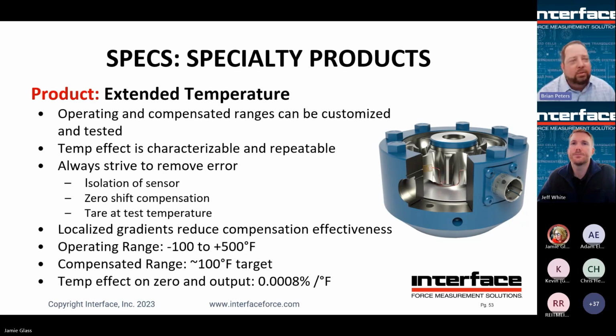Also to keep in mind here, sorry, Jeff, I'll run with this. There's a cutaway here in this model. And if you look to the left of the cutaway there's a little bit of a pocket. It's important to note how a sensor is actually temperature compensated. We have specs. We tell you it's going to meet a certain level of temperature change. But you need to remember that's assuming a homogeneous temperature profile, right? So if you have a temperature gradient that is localized, maybe it's coming through the load string, for example, which then transfers through the center hub, through the beams, then eventually reaches the outer ring. Very different than if the whole load cell is brought up to temperature, right? So the compensation effectiveness may vary, especially if you have, let's say, a hot or cold airstream right on that little machine pocket. That's where we finish out some of our zero comp, and we do our temp comp.